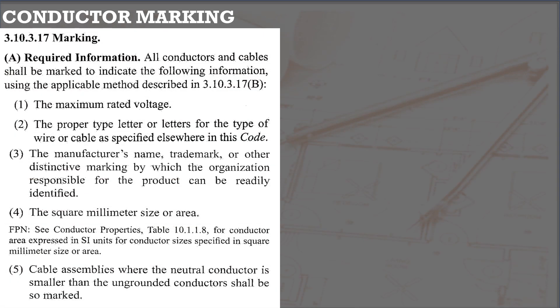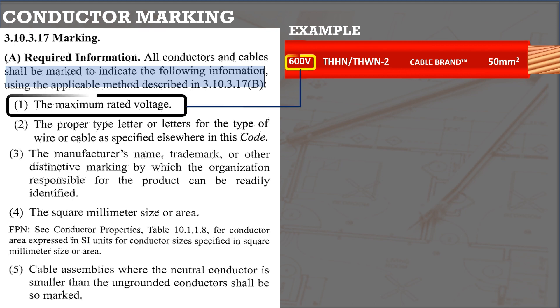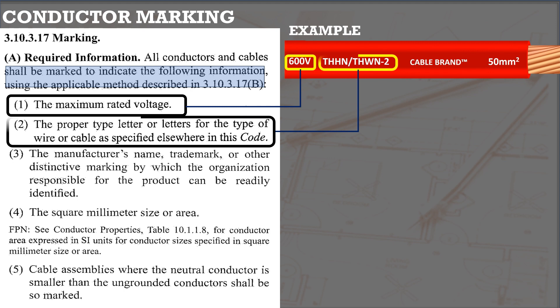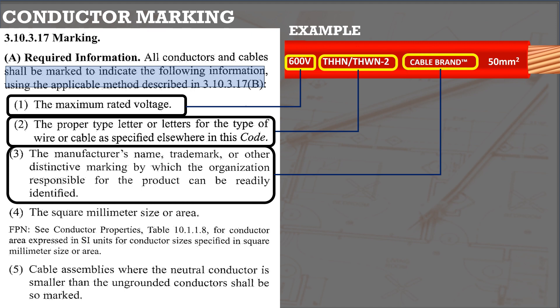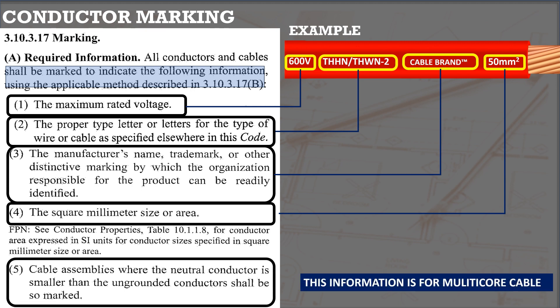All conductors installed in a building must be listed as specified in Section 3.10.3.17 marking. It notes that all conductors shall be marked by the manufacturer. The sample conductor shown is a single-core conductor. If listed, we can find the following information: maximum voltage, insulation type and temperature rating, manufacturer's name or trademark, conductor size or area — in the Philippines we use squared millimeters, while NEC uses American Wire Gauge — and for cable assemblies, applicable to multi-core conductors.